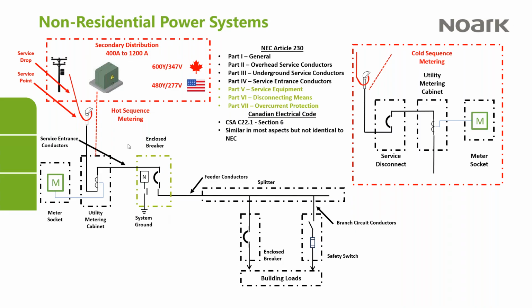Okay, so then the power moves through feeder conductors. And in this case, I'm showing a splitter box. What you see here could be replaced by a switchboard or by a panel board. But functionally, they all operate the same way. The feeder conductors come into some sort of splitter device, and then the branch circuit protection devices protect everything from there out to the loads.